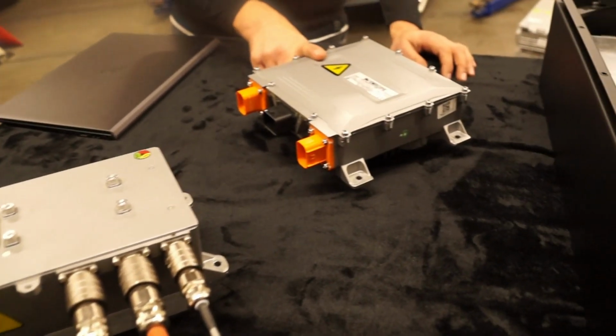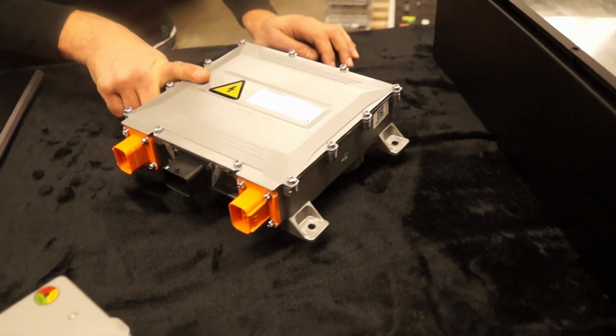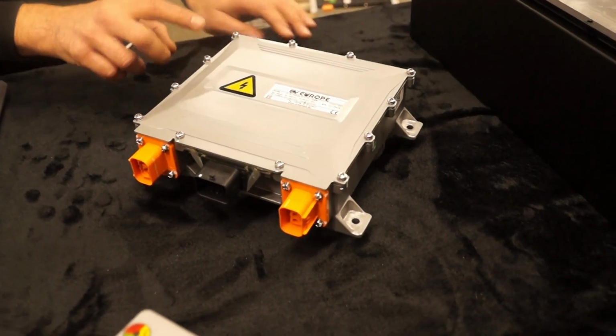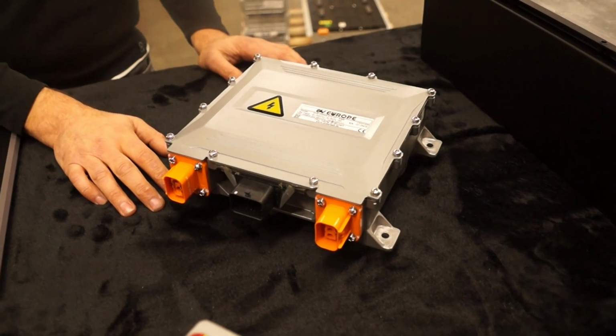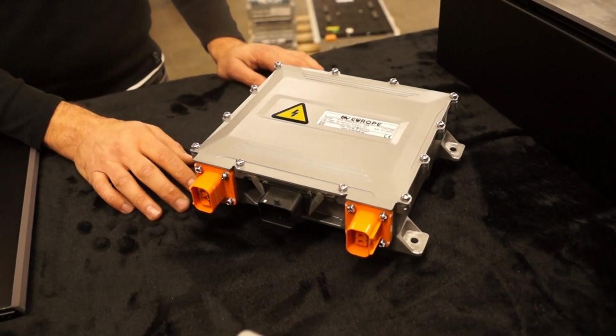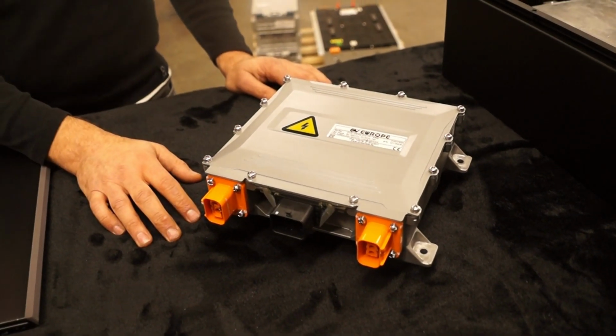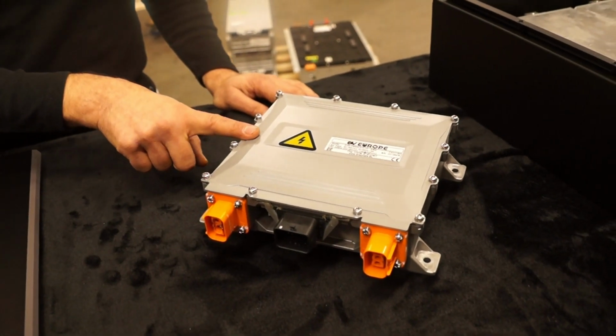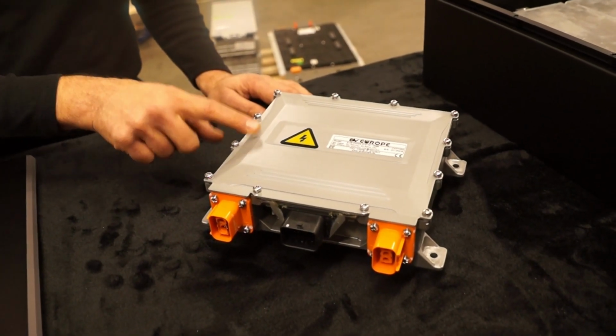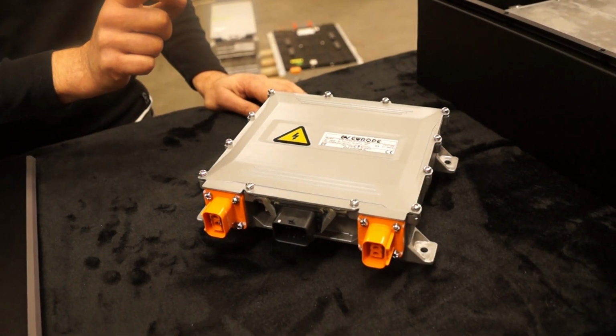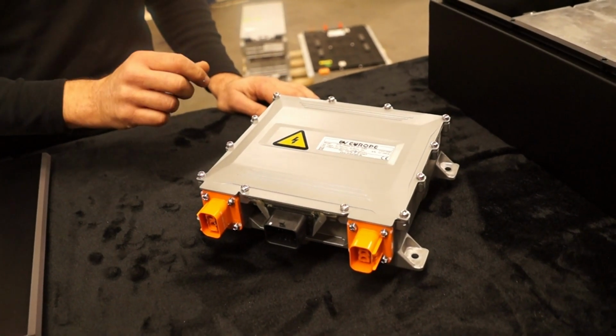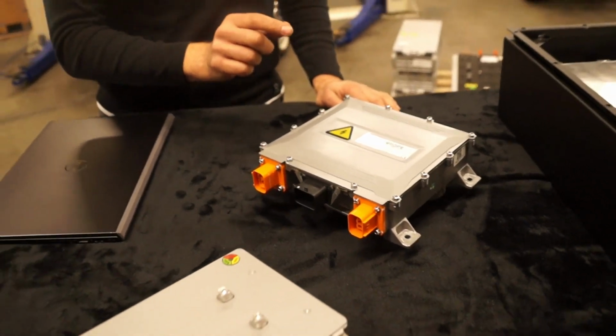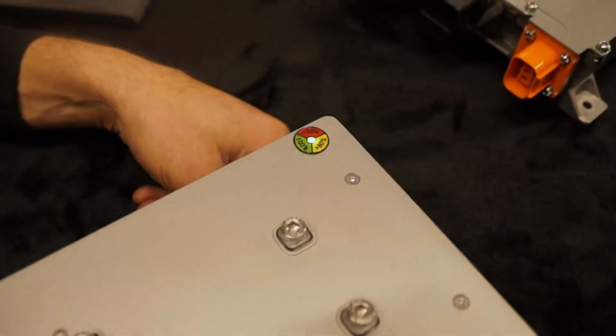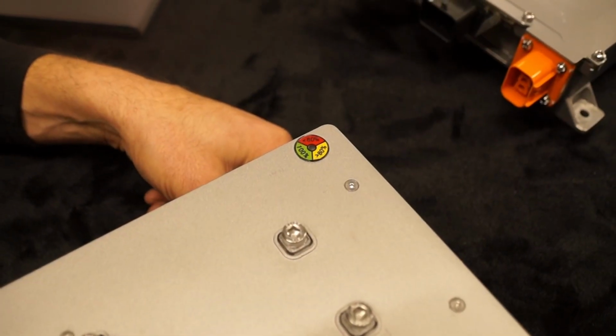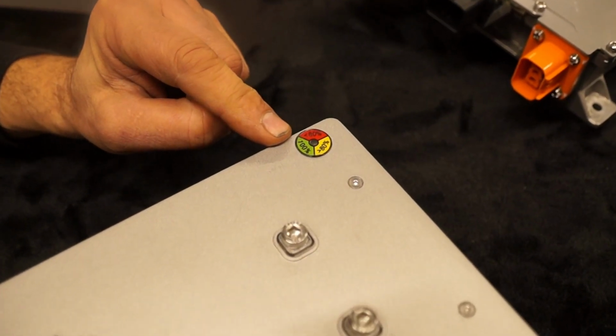On the OEM4 charger, it's a bit more complex, because here you don't have any LED, any indications at the outside of the charger. But there's one small thing you can notice. As soon as you have AC power connected to this charger, you will hear a very light click. You have to listen very carefully, but you will hear the click. If you don't hear it, then you can also check your AC power.